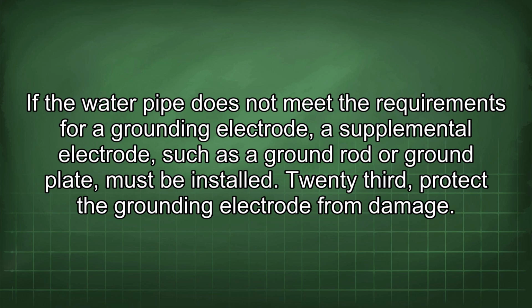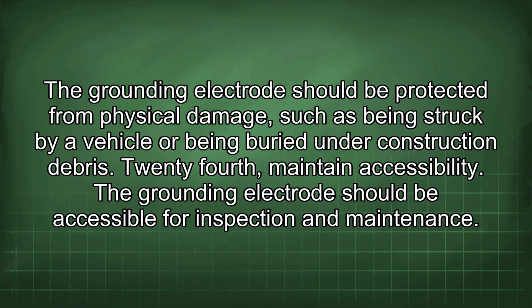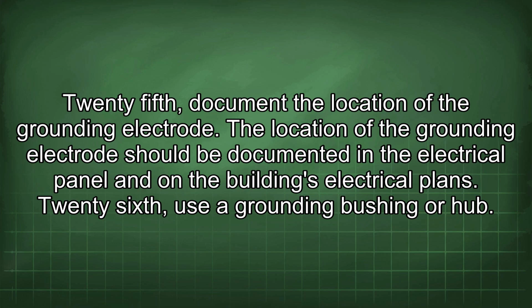23rd, protect the grounding electrode from damage. The grounding electrode should be protected from physical damage, such as being struck by a vehicle or being buried under construction debris. 24th, maintain accessibility. The grounding electrode should be accessible for inspection and maintenance. 25th, document the location of the grounding electrode. The location of the grounding electrode should be documented in the electrical panel and on the building's electrical plans.